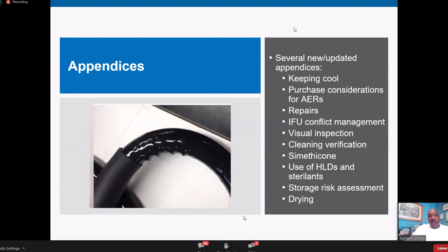Visual inspection, cleaning verification, as we talked about throughout the document. Simethicone. Not sure if anybody's had this conversation, but this was a big topic that was discussed, and the use of simethicone during cases. That is discussed in this update. The use of high-level disinfectants and or sterilants. Storage risk assessment. Again, I'm quite sure everyone from the 159 participants on the call has different hang times that they hold their scopes before they use them. It talks about the storage risk assessment and what that looks like when determining how long you will store your scopes. Drying, that's also in there, and what that means and what that looks like.